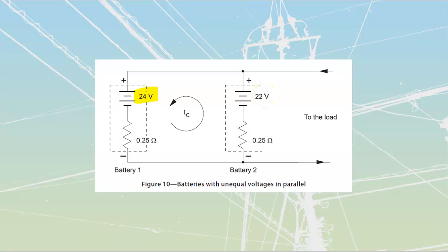This diagram shows the formula: they take the volts difference divided by the resistance of the components, 0.25 of an ohm, the resistance of the path. That tells them the size of the circulating current. In this case it's not huge, it's 4 amps, but it still causes some problems inside here.